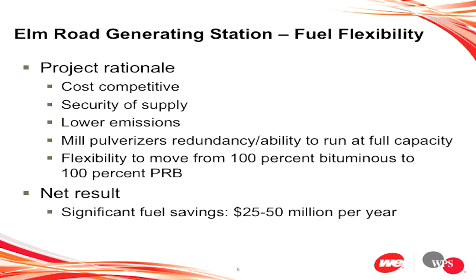Mill pulverizer redundancy: the units were built with 5 pulverizers each. We can make full load with 1 spare, but when on 100% PRB, you need all 5 mills in to make full load. If we have an overhaul, we now have the ability to blend, going back to 40% bituminous coal, taking a mill out, and still making full load. Depending on the value of energy and capacity, the market may want all 5 mills in, but if one's out on outage, we can still give full load on 4 mills with a blend, even though that might have an energy cost impact. That's the flexibility I'm talking about.